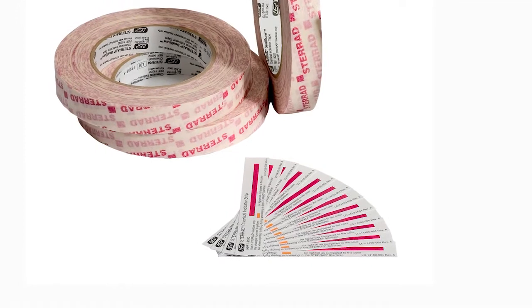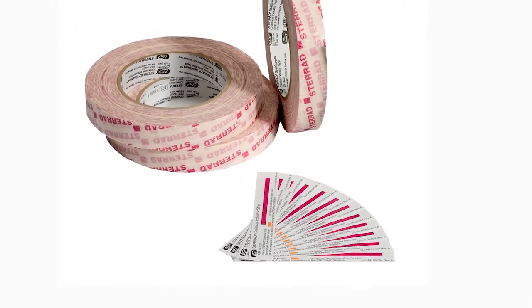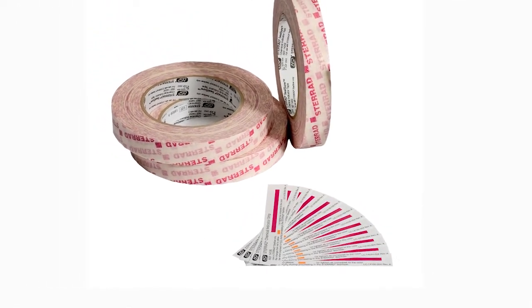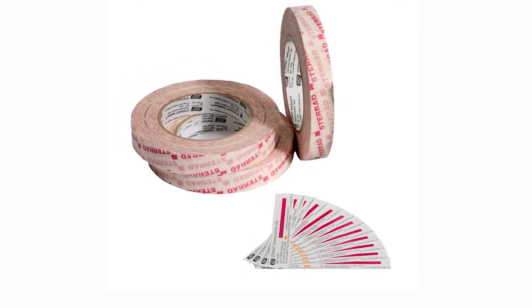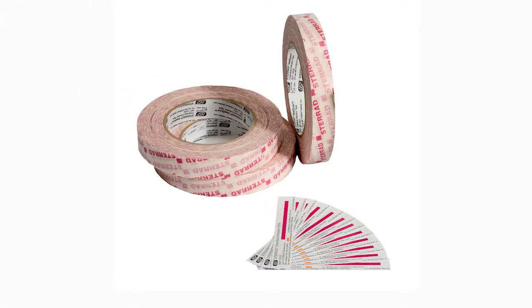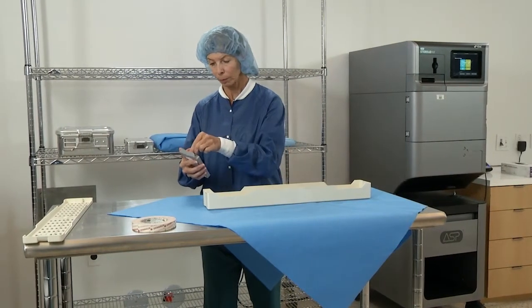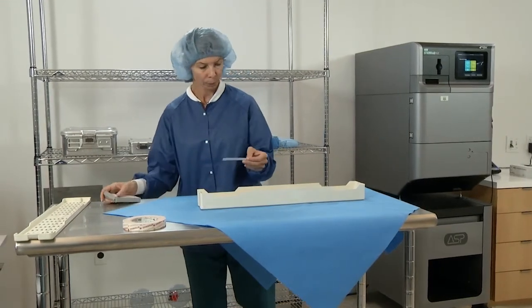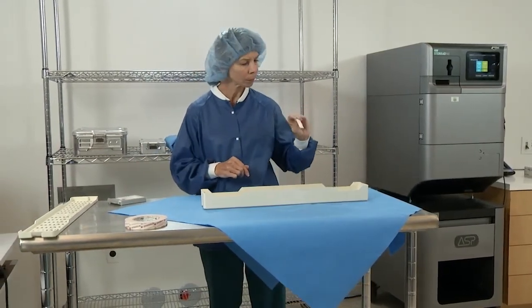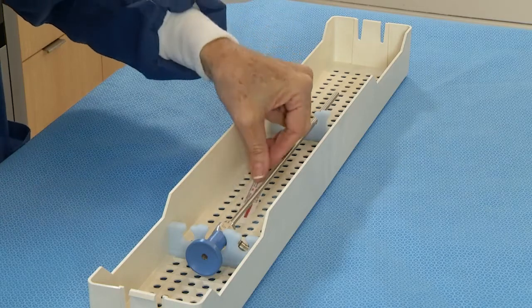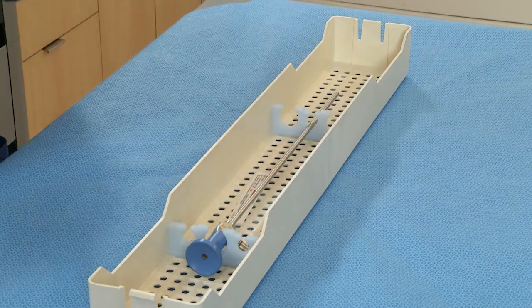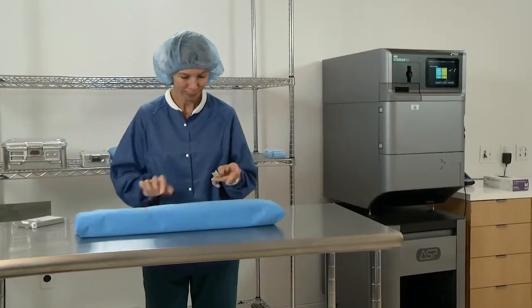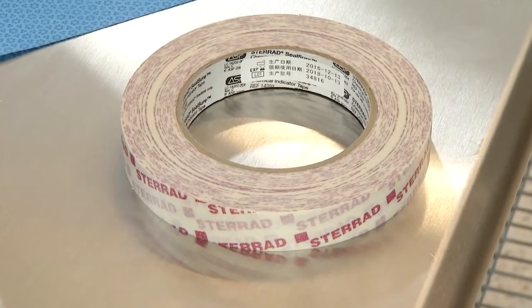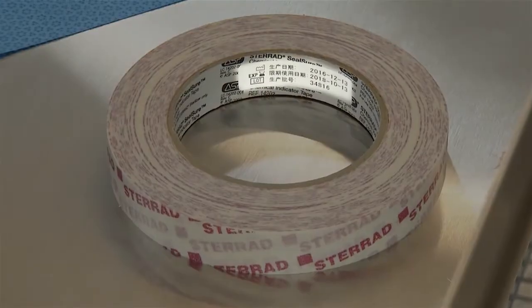STERRAD chemical indicator strips and STERRAD SealSure chemical indicator tape offer a method to verify that the load has been exposed to hydrogen peroxide in the sterilizer. Chemical indicators are not a substitute for biological indicators. Place a STERRAD SealSure chemical indicator strip inside the tray, container, or pouch. Notice that the lot number and expiration date are not printed on each individual STERRAD chemical indicator strip. Secure all wrap trays with STERRAD SealSure chemical indicator tape. The expiration for the indicator tape is located on the inside of the roll.